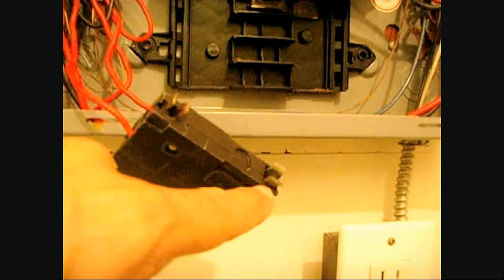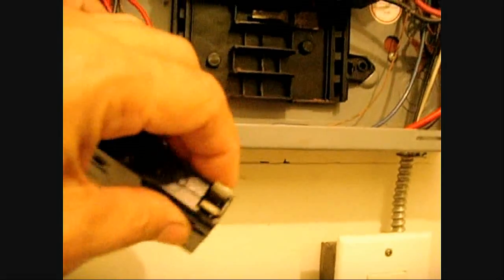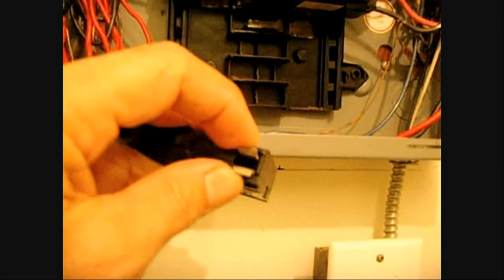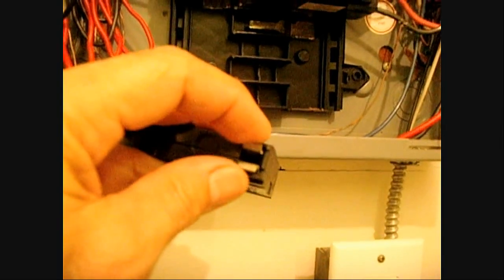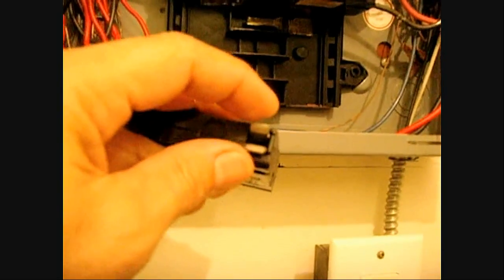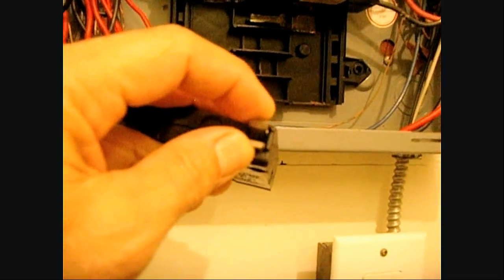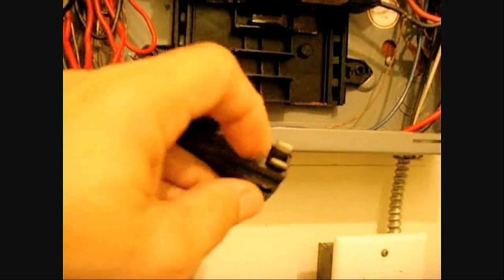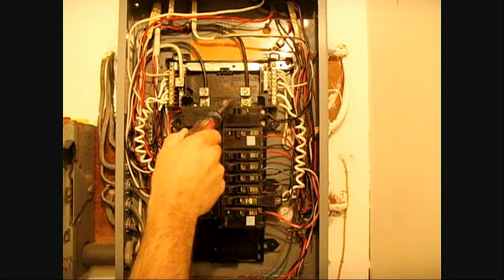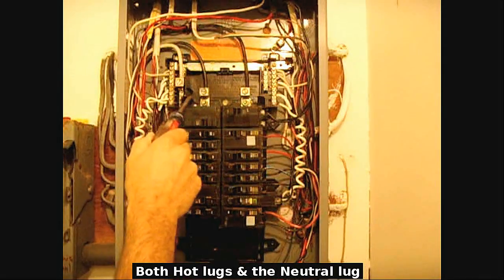Brush a little bit on here, and if you want, you can also take a needle nose and squeeze this a little tighter. And I would actually suggest you doing that. By making this tighter, don't overdo it, just make it a little tighter. It'll make a better connection when you pop it back into the panel. You want to make sure that these connections here are also very clean.